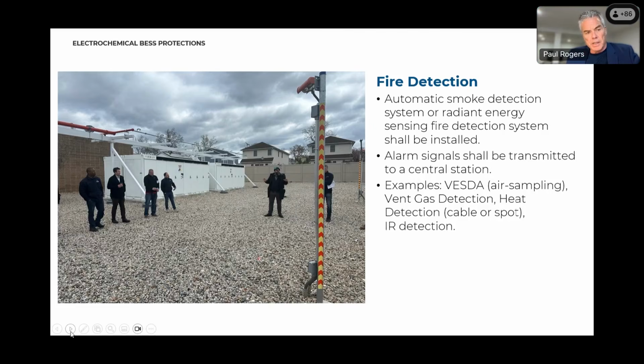Fire detection. Again, this wasn't required in the original code, but now we have, well, fire detection was, but a central alarm station was not required in there. And a central alarm station, for those who don't know, is basically something where you activate a fire detection system, and it will send a signal to a 24/7 monitored central station, which will actually dispatch the fire department. And that's important. And that was a big deal to get that moved forward. Even the NFPA 855 standard does not have that requirement for cabinet style systems themselves. But the state put that in there.